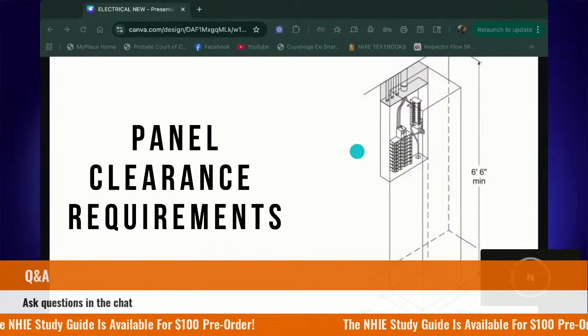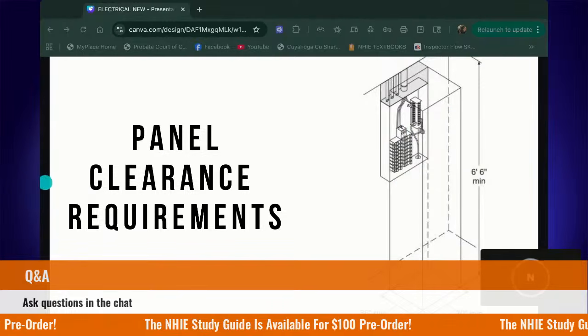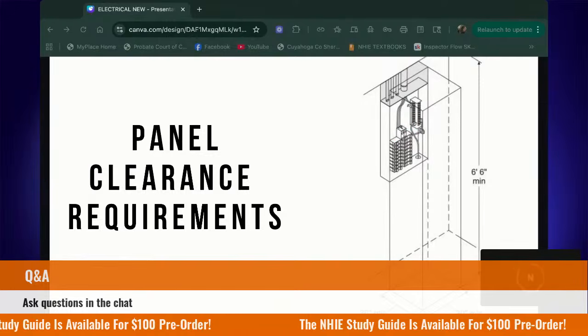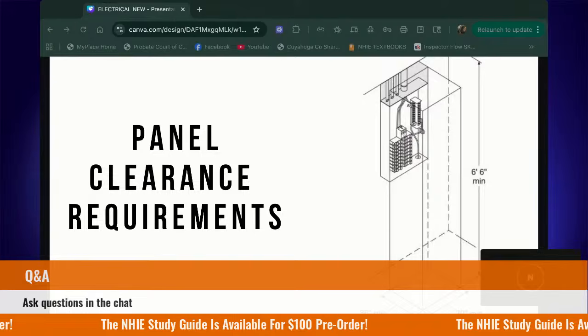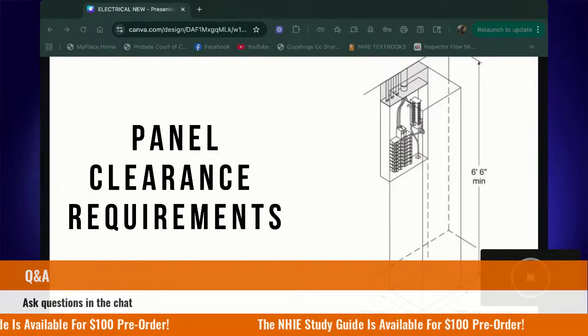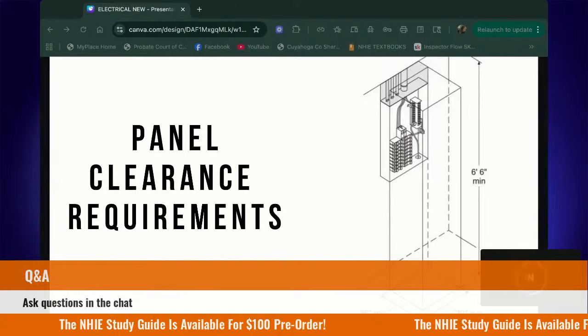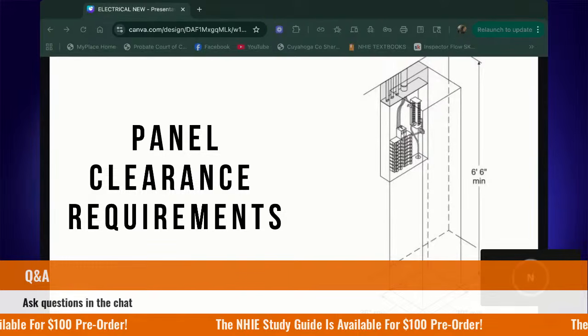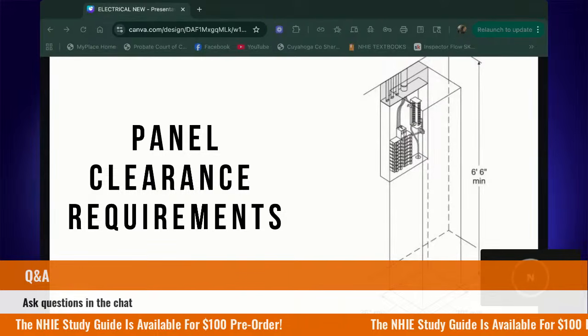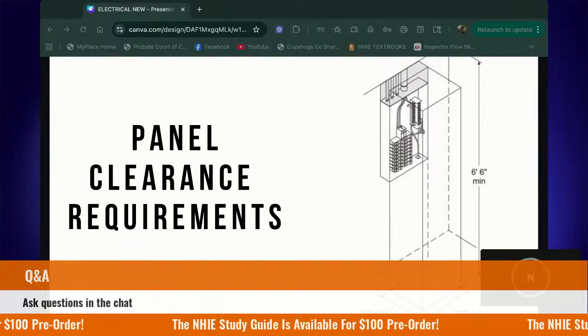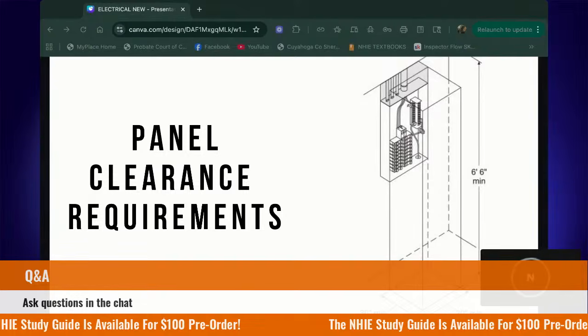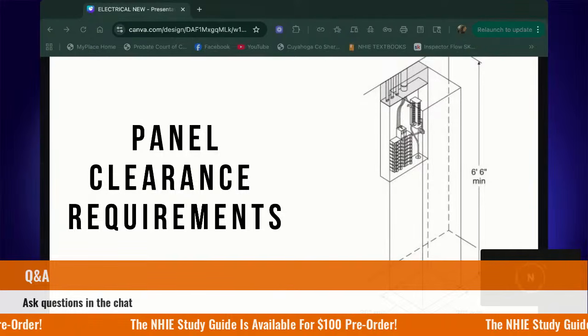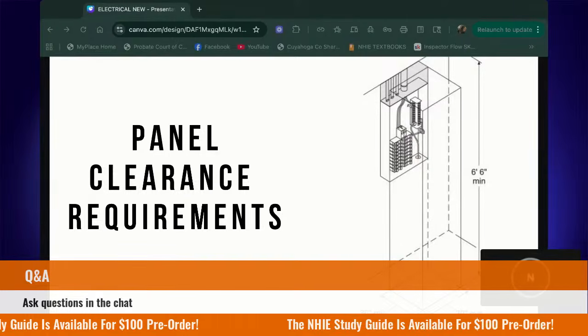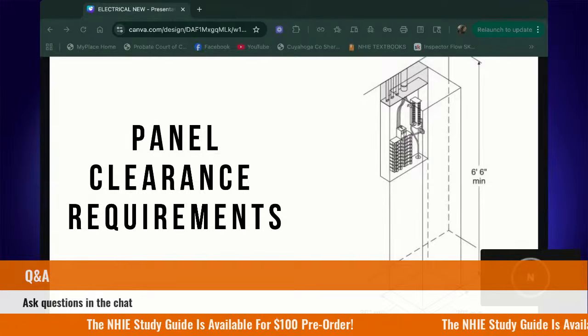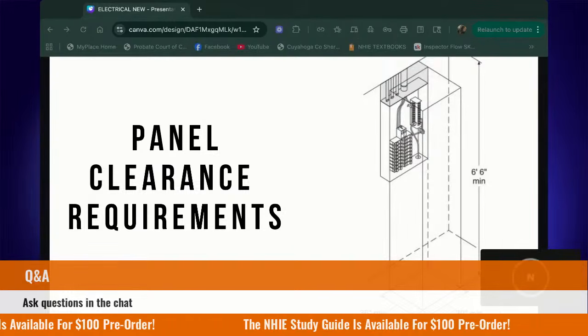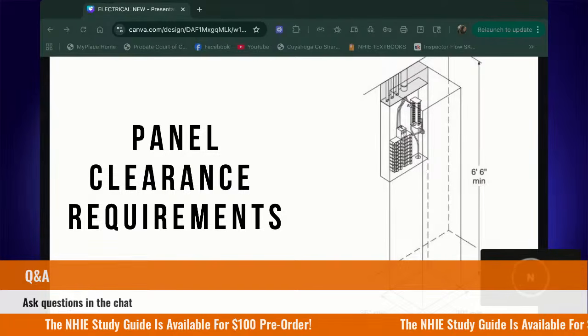And then the door swing for your panel. The panel has to be able to swing open 90 degrees. For your inspection purposes, the panel has to be accessible to you without having to move furniture, old appliances, personal items, basically. You should be able to walk right up to the panel and open it up freely, and the door open at least 90 degrees, and it should be reachable as well. I forgot to say, your maximum breaker height is 79 inches because they don't want you to have to stand on a ladder to be able to access the breakers in case you had to shut it off. Sometimes panels are locked, but they're supposed to have easily accessible keys. All of these are either defects or limitations.